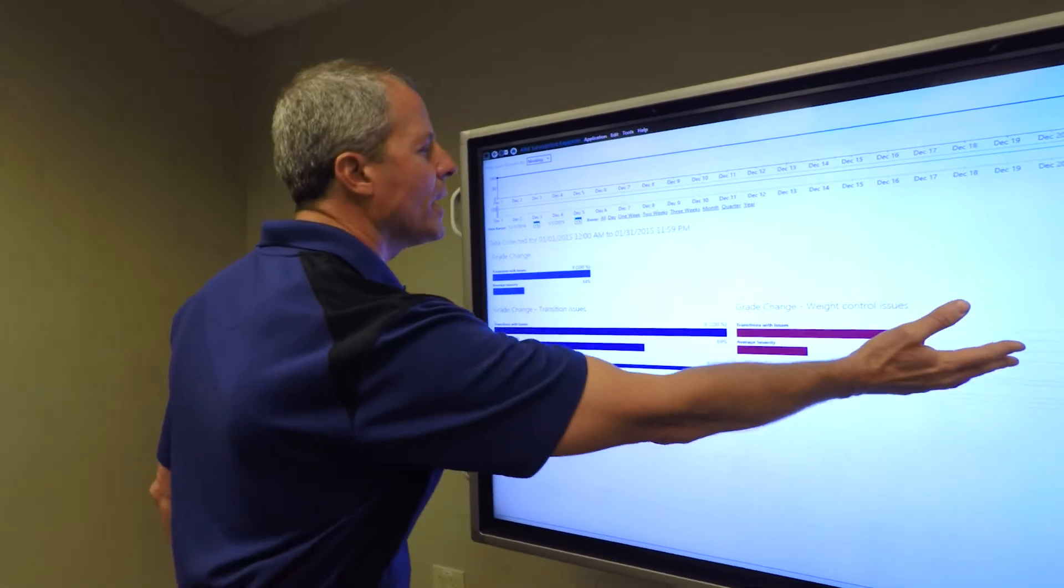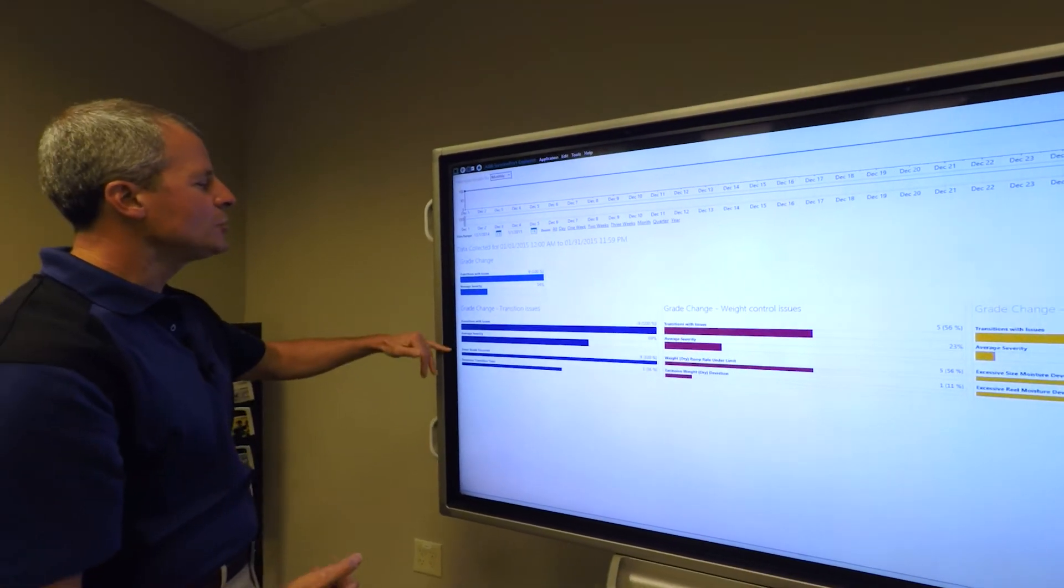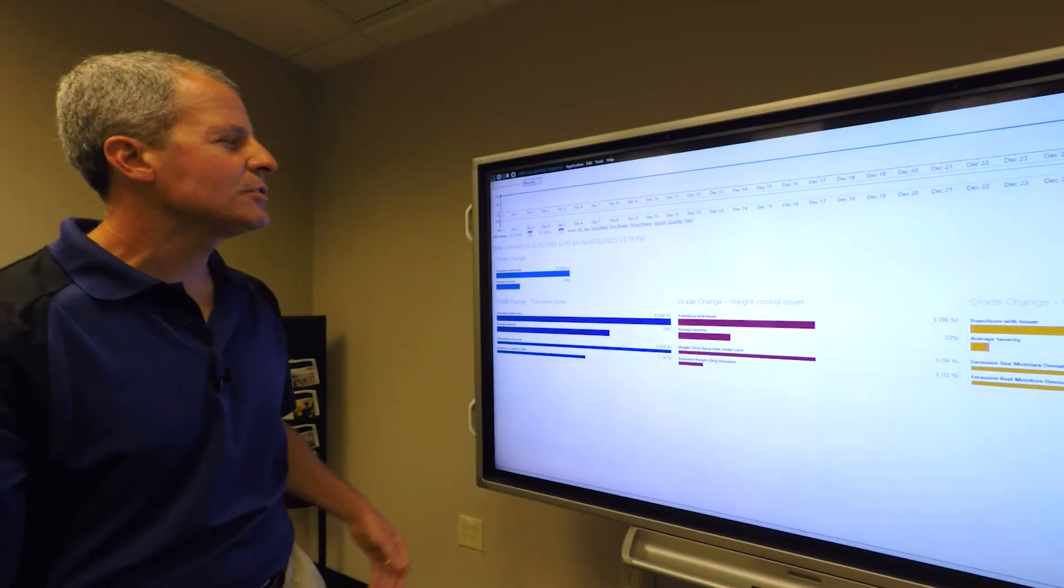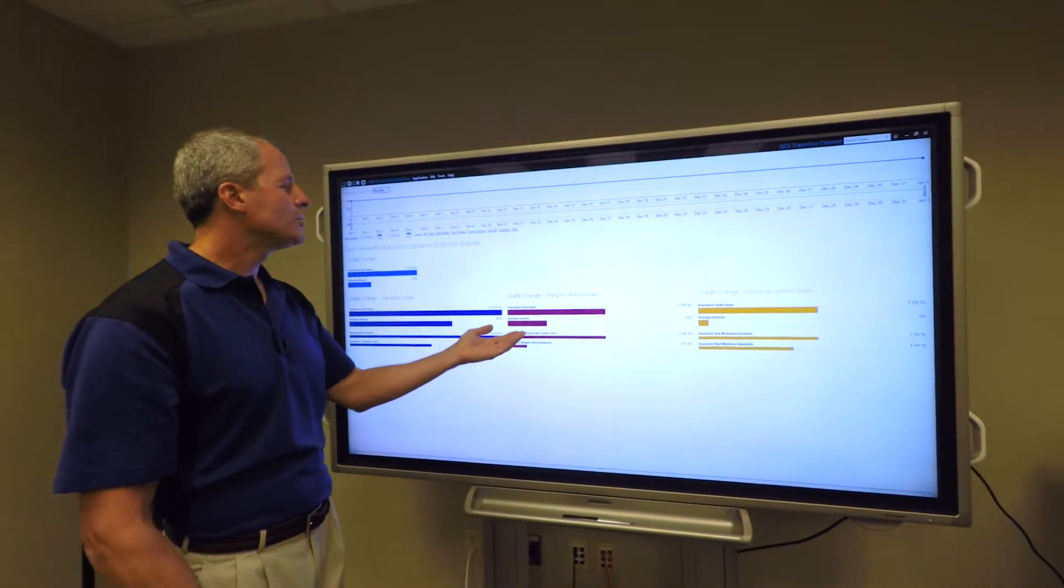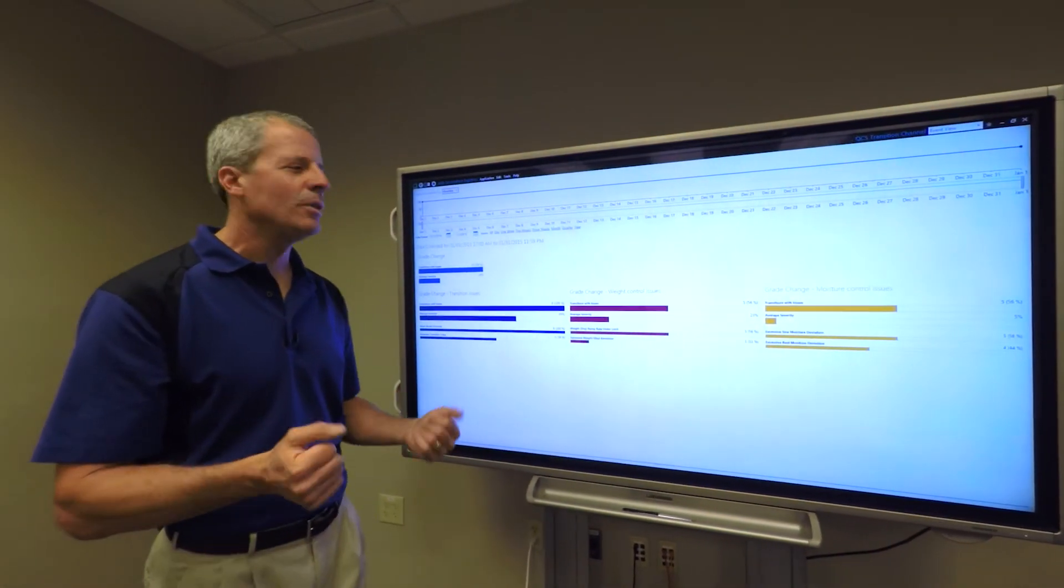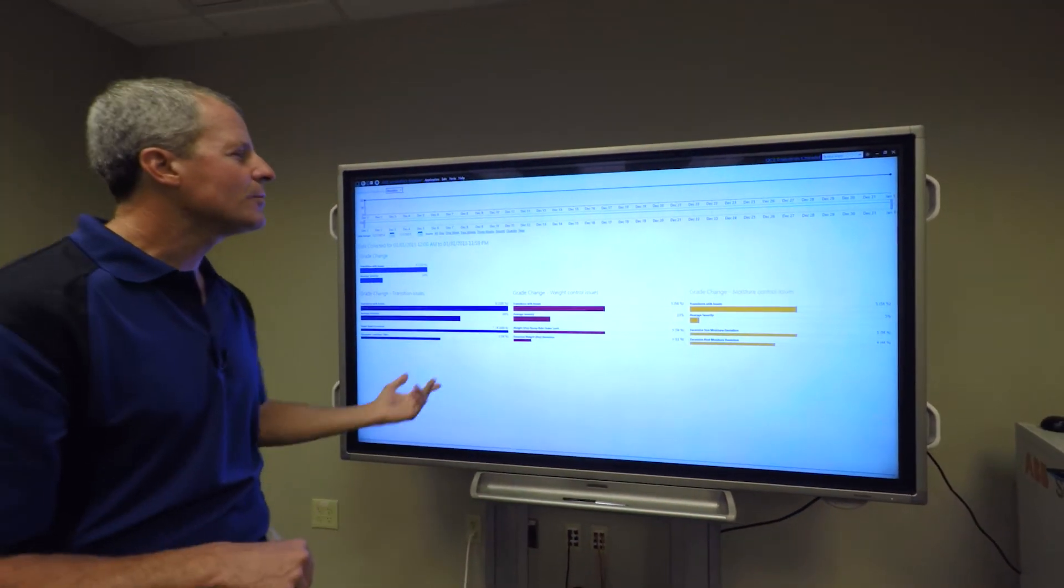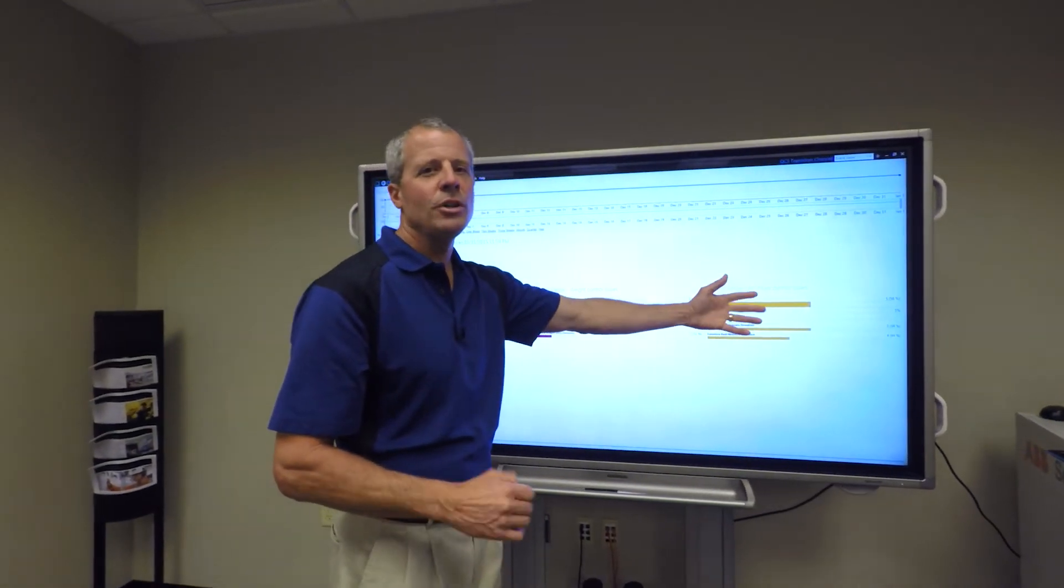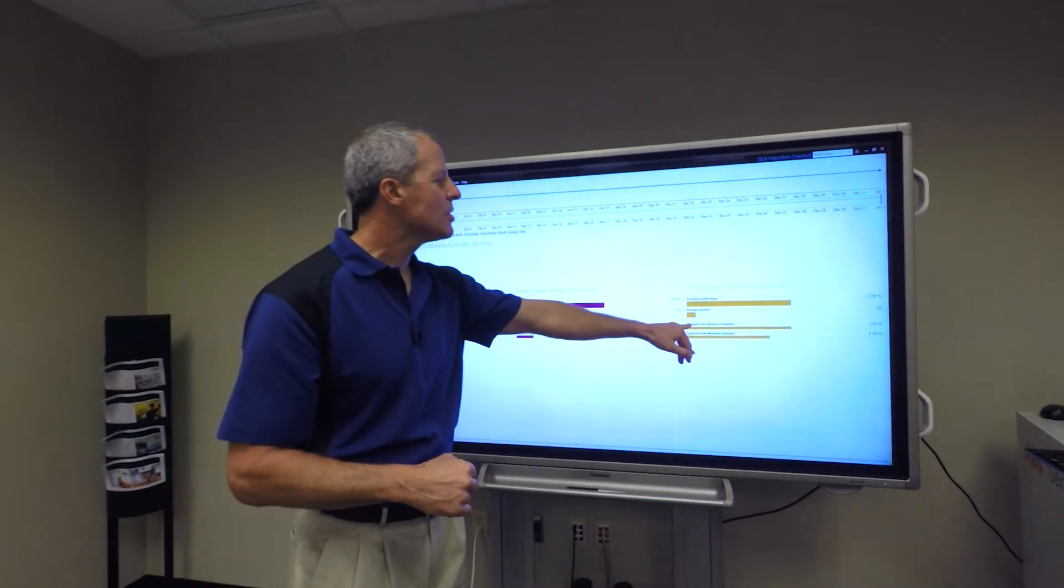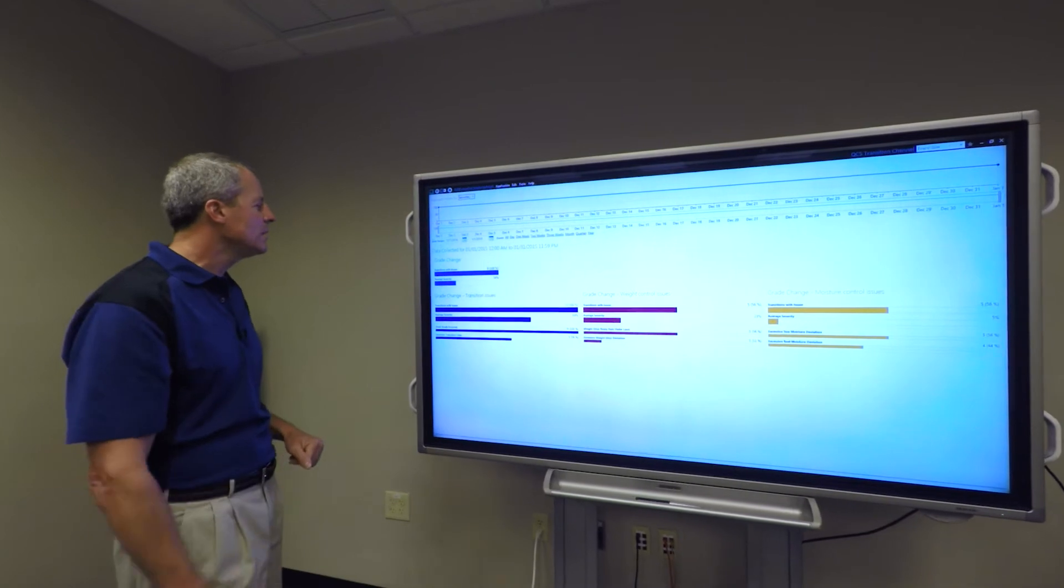If we look at those transitions, there's KPI breakdowns. We look at overall transition issues, we look at the time, we look at whether a sheet break occurred during the transition. We can also look at weight control: Was the weight change ramp rate fast as what we thought it should be? Was there an excessive deviation in the weight measurement from target? And at the same time, moisture is a big one on grade changes. If we have an excessive moisture deviation during the grade change, this can cause potential issues with sheet break or runnability.